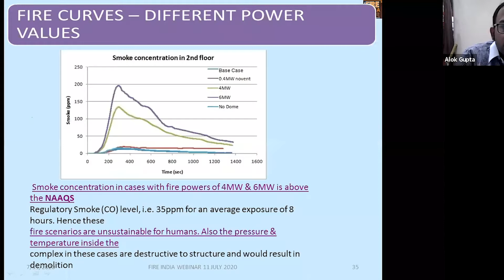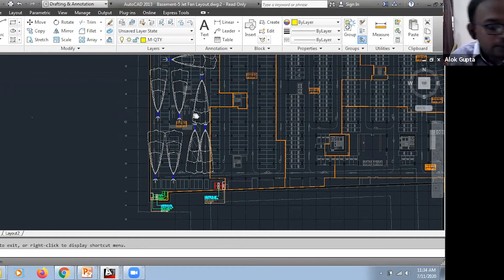In the same mall, we have seen jet fans installed in different basements with different installation methods. Jet fan manufacturers claim that once you install the jet fan it extracts the smoke. Jet fans are definitely a good system, but whether they function properly or not, we can easily simulate and understand the positioning, the inclination, and whether any vortices or smoke pockets are formed due to the jet fan installation.